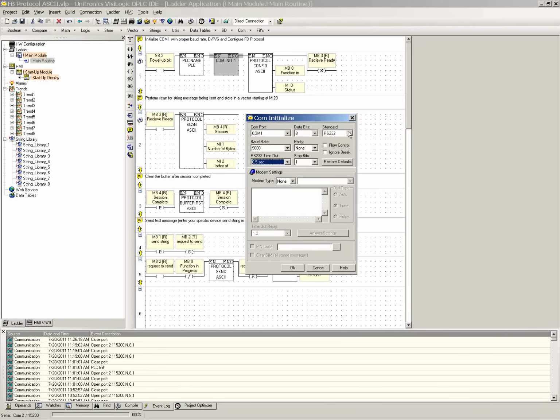You need to make sure you define your PLC port to be the correct one that you want to use, and it's also important to mention that when you change the COM ports, you need to make sure you change the jumper settings inside the controller. So it's software defined, and yet it is also hardware defined as well. They're actually dip switches, not jumpers, but they're dip switches that you need to define for RS-232 or 485. We support both of those physical mediums over the serial communications.